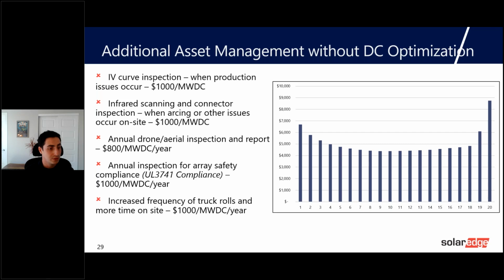Most often we would expect this type of issue to occur in the commissioning phase or at the end of life, and as such, we've modeled it using a bathtub curve. The same goes for infrared scanning and connector inspection. This is if arcing or ground faults are noticed at some site. For example, in the SolarEdge optimizer solution, we have the Sense Connect feature that Kleber mentioned earlier. The Sense Connect feature is going to cease inverter operation and lower array voltage automatically if connector issues occur. And so there's no need to do infrared scanning or visual inspection to figure out where there are issues. Again, this is expected to happen more often in the early and late stages of a system life, so it's modeled with a bathtub curve.